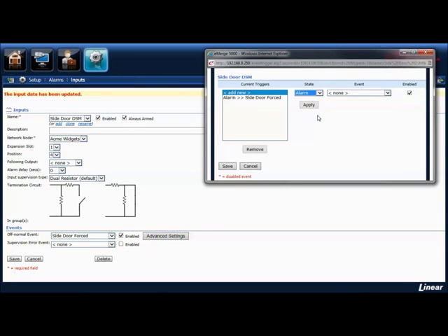The alarm event is triggered by the input going into alarm. The normal event is triggered when the input goes back to normal. The open event is only available when using a supervision type of series or parallel. This event is triggered when the input circuit has a resistance value of infinite. The shorted event is only available when you have configured the input for dual supervision and is triggered when the input circuit has a resistance value of 0.